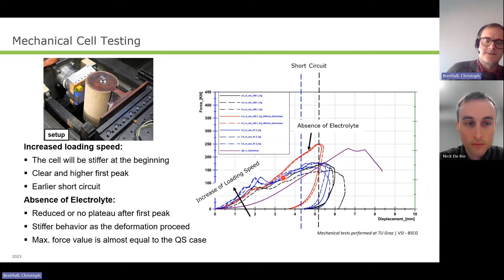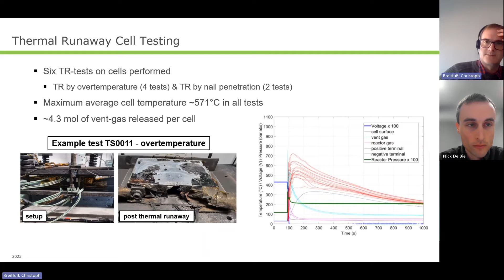Now we come to thermal runaway testing of the cell. We did 6 tests in total, using different thermal runaway initiation methods: over-temperature by heat bed in 4 tests, and nail penetration in 2 tests. There was no significant difference in the test results, so all tests were very similar. The maximum average cell temperature was 570 degrees across all tests, and on average 4.3 mole of vent gas was released from the cell.